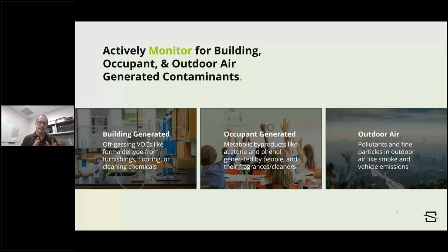What's important about that as it relates back to the code is now you get a really good picture, and it hits all the buckets that ASHRAE has designed for and wants within indoor air quality. When you read the IAQP, one of the things it talks about is they want an assessment of all the contaminants, not just the contaminants related to occupants. And so for that reason, we can measure what's happening with the building off-gassing, principally through formaldehyde. We can measure all the pollutants that are coming in from outdoors, whether it be smoke or vehicle exhaust or what have you. And also, obviously, the bucket related to occupant-generated contaminants. That now gives you a really good picture of how clean your air is. And now you can understand why they said in that user manual, this is a more direct approach to the goal of air quality.